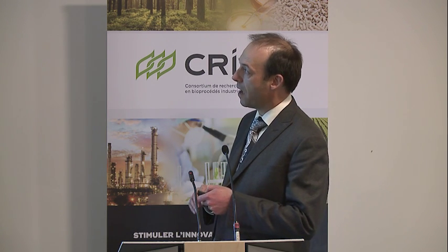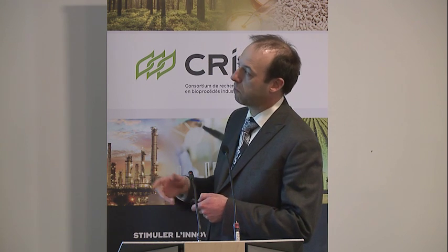So let's go to this slide in a few seconds. Here is the raw material arriving. We have here the fermenters and the purification center. If you want to go from one room to another one, you will need some SAS. So we have SAS here, and we control the air pressure between the two rooms to avoid any contamination again. We have a control room here also, so we have to control the personnel, how a person can pass through the door from one room to another one. We need to control the access to those rooms again. So it's a short demonstration of that.